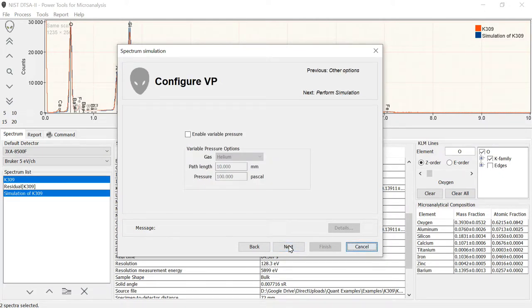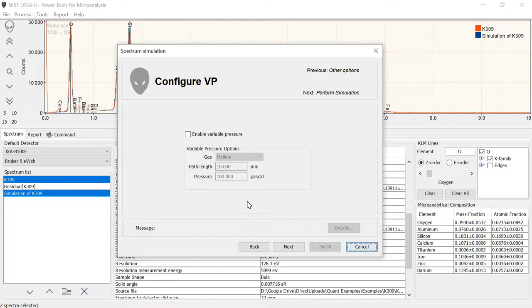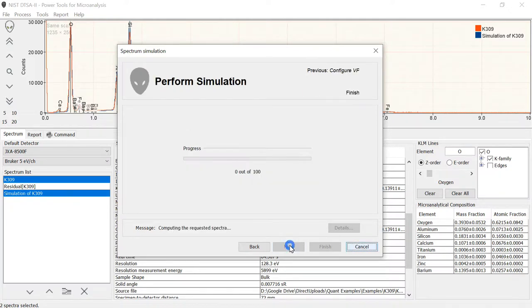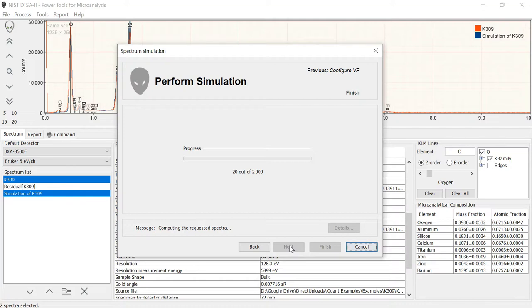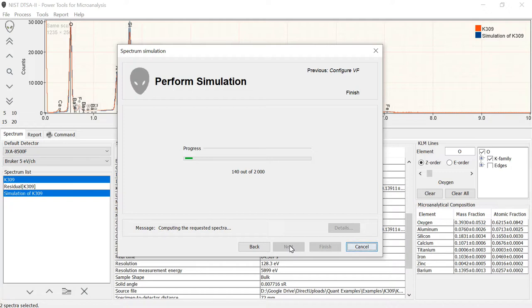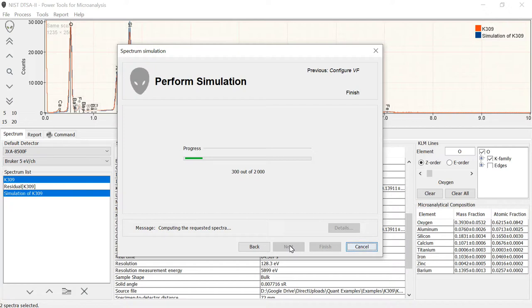One of the options too, this is good for learning about why you shouldn't do quant in variable pressure. I'm going to not enable that option for this example. OK, I click next and it starts computing away. As I said, the model takes a while to run. The reason for that is that the model is actually tracking simulated trajectories of electrons through the material. And then at each time that the simulated electron scatters, performs an elastic scatter off one of the atoms, it also considers whether an X-ray was generated in that last piece of trajectory.